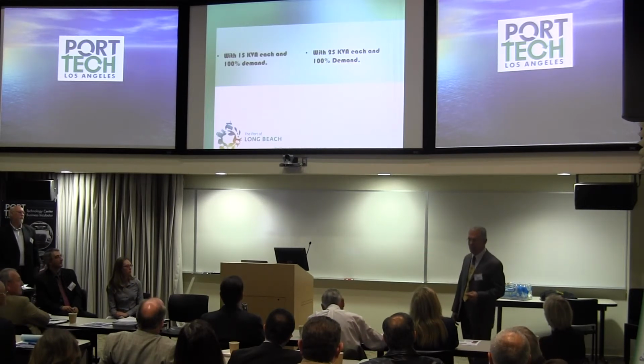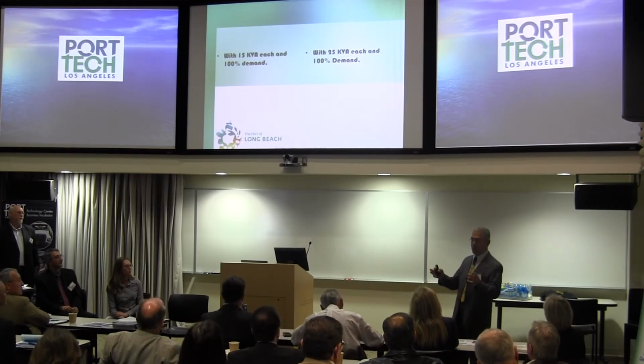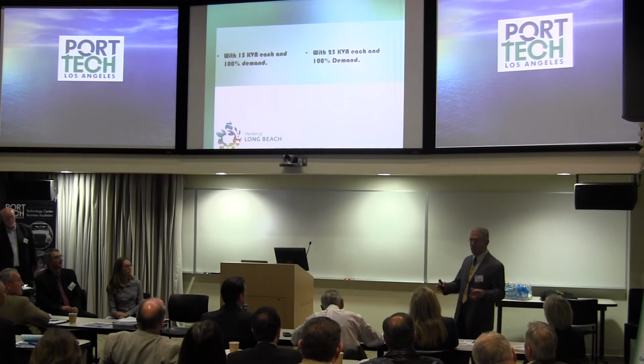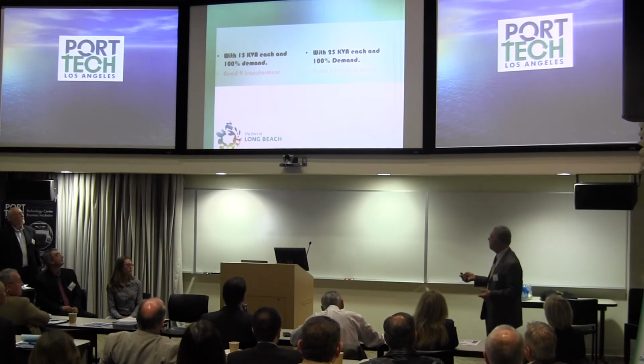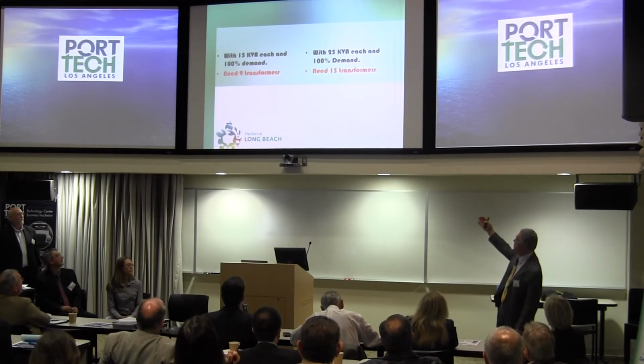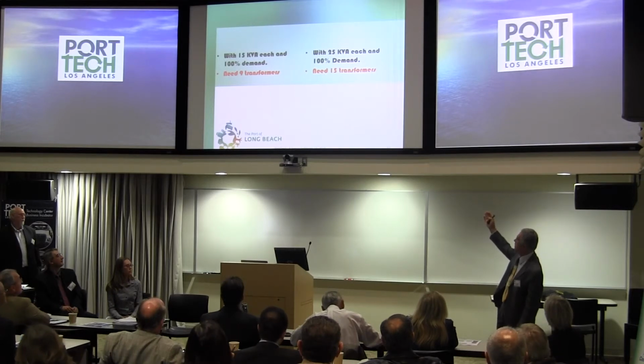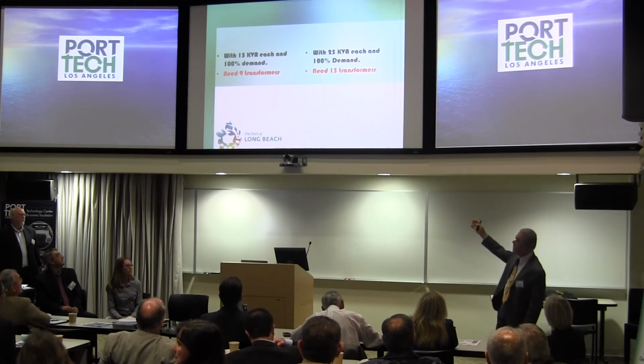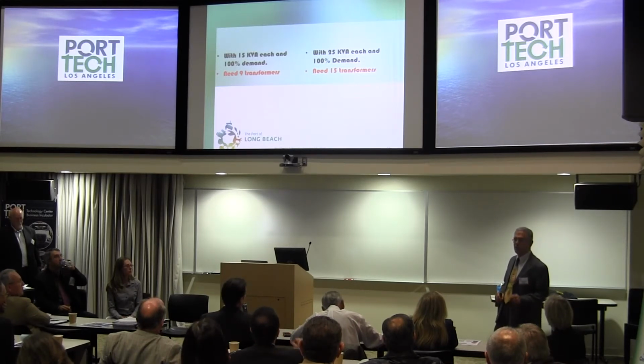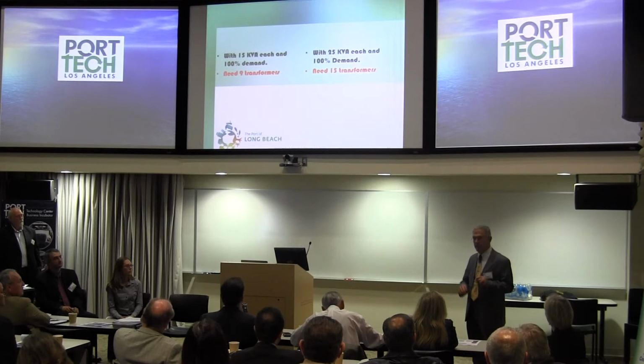But in this analysis here, 100% demand means all the reefer plugs have a container plugged into them, and they're all drawing 15 kVA each. It's an unreasonable assumption, but it's done often. So that's one thing to keep in mind. But keeping those numbers together, even then you can see that with the right number, you have 9 transformers. With the wrong number, you've got 15 transformers. 6 extra transformers that are doing nothing more than the 9 transformers you have at the installation. Nothing more. Okay, just think about that.